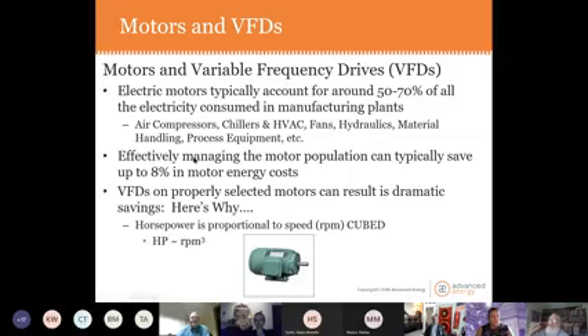Motors and variable frequency drives. This is a great area to focus on. Electric motors typically account for 50 to 70% of all the electricity consumed in a plant. In air compressors, chillers, HVAC, fans, hydraulics, material handling, you name it, there's motors everywhere. And we've implemented motor management programs and saved roughly between 6 and 8% of the total energy consumed by motors by looking at things like having a policy to buy the best motor, the most efficient motor and things like that.